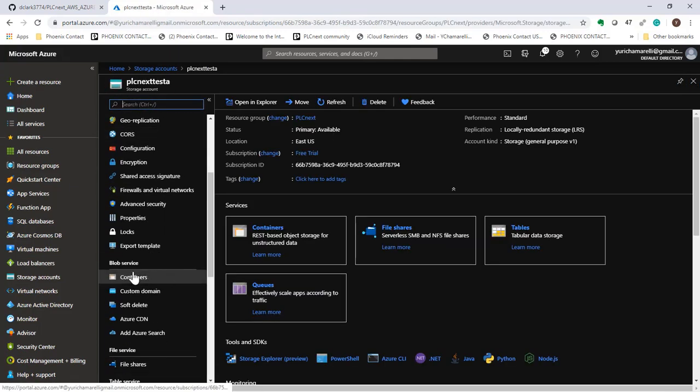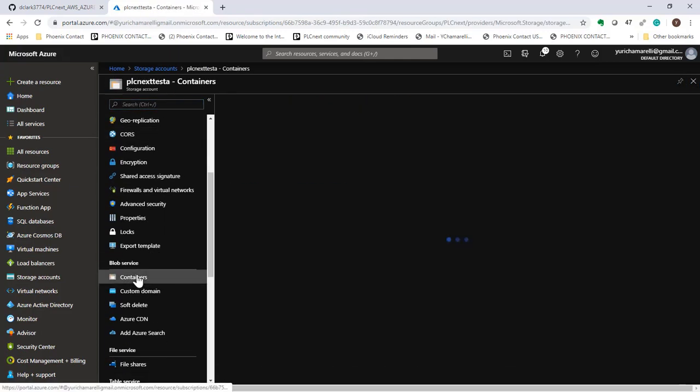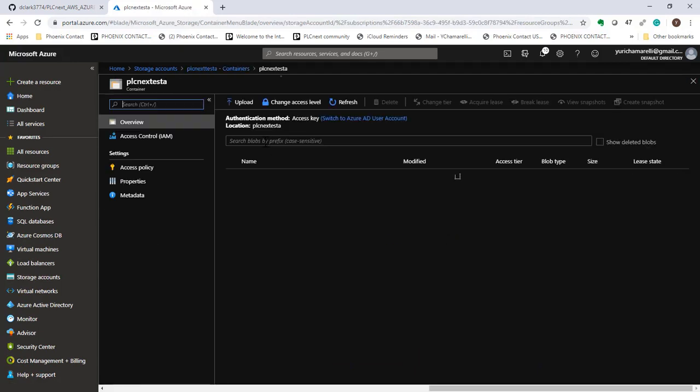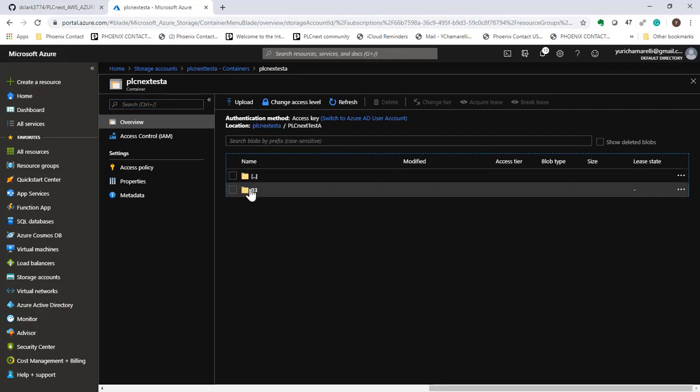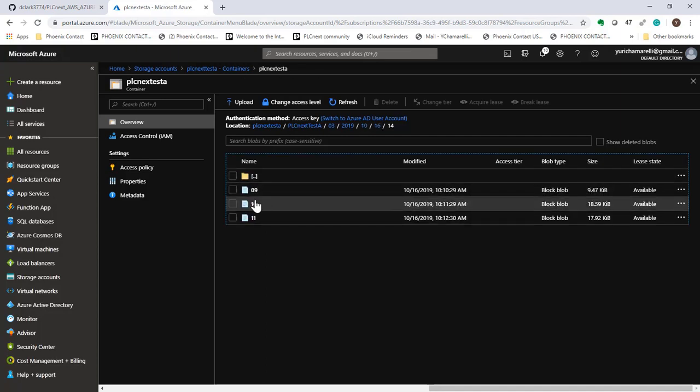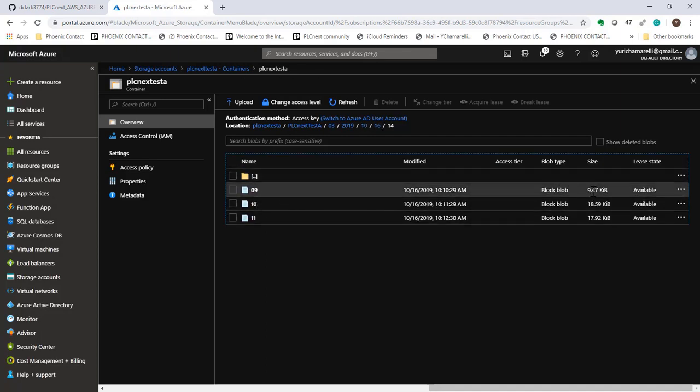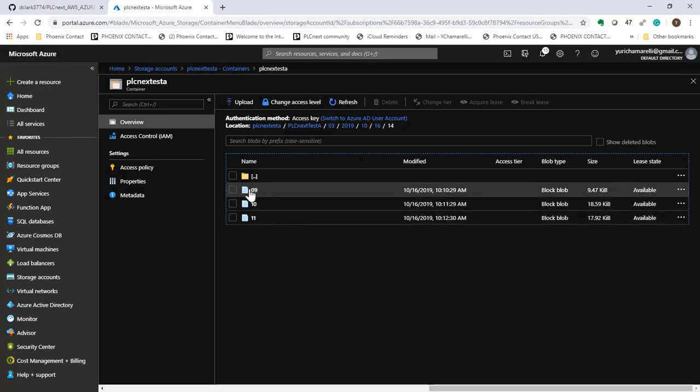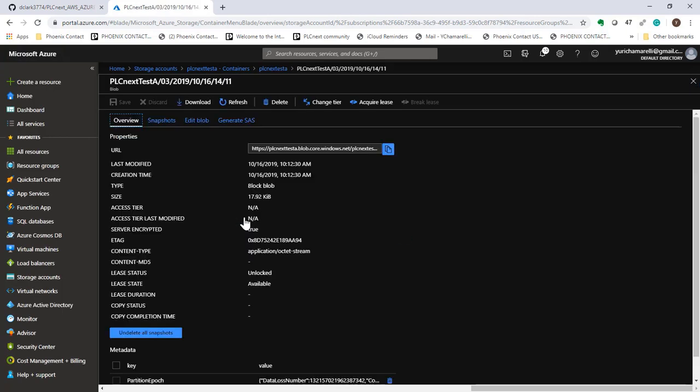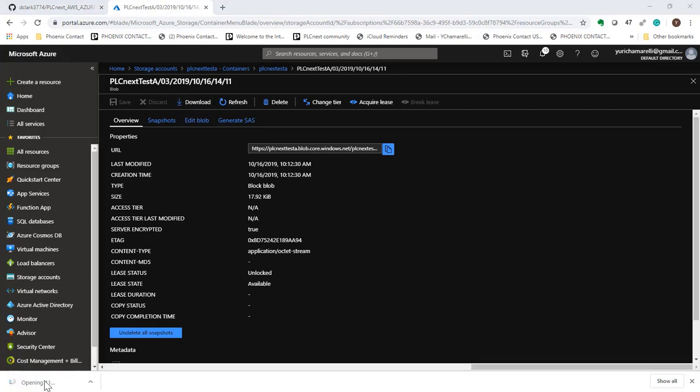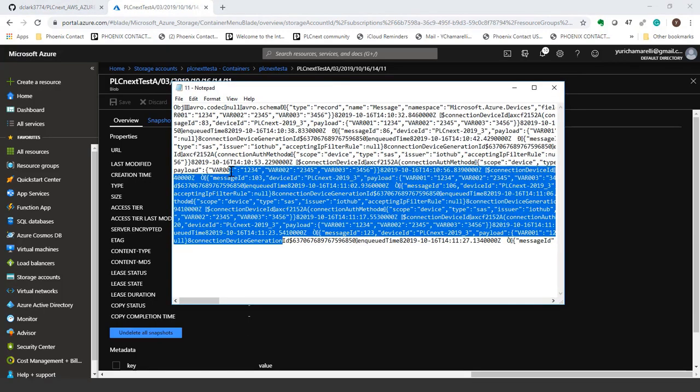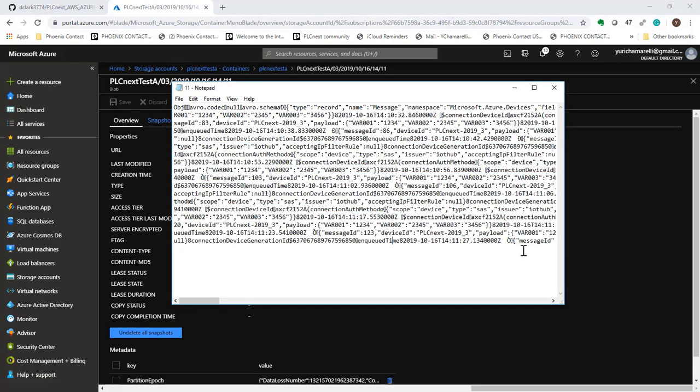PLCnext. And under your containers, you will see that some data is getting there. The data will take at least 60 seconds to get there. It is collecting data every one second from the example code. Every 60 data reading operations in the file, you can download and compare the data. To open the file, use WordPad or anything else that can read it. You should see the data that is being saved is the same as the blocks are sending in the program.